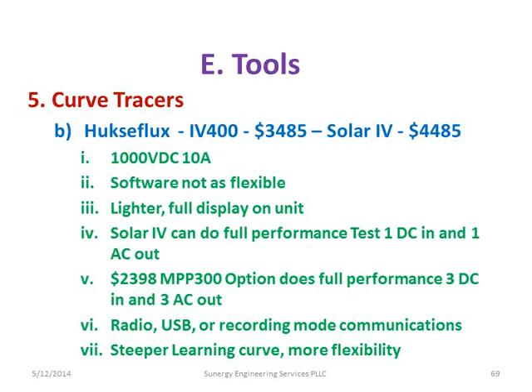They have 2 models. A lower model that just does curve tracing, and the model I have up here also does power performance, AC in, DC in, AC out of the inverter, one channel, which is really an added feature. It's all in one piece, a lot lighter, and has a lot more flexibility. There's a lot of things you can adjust when you do the test, which means there's a lot of things you can screw up.